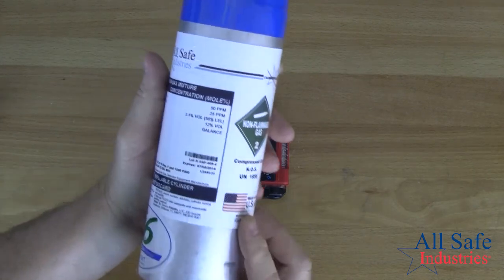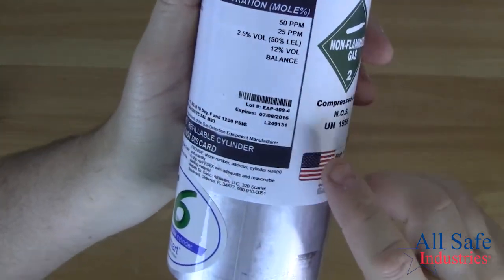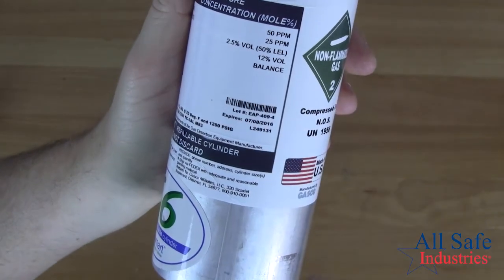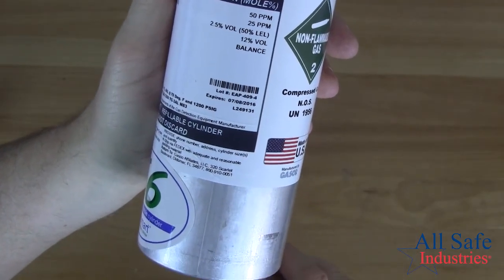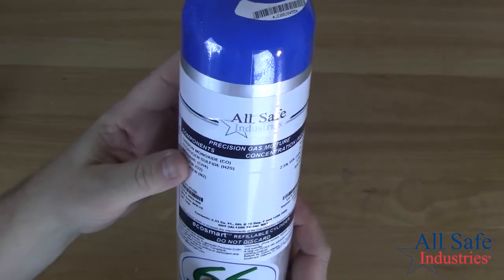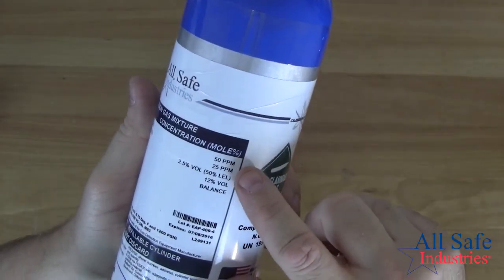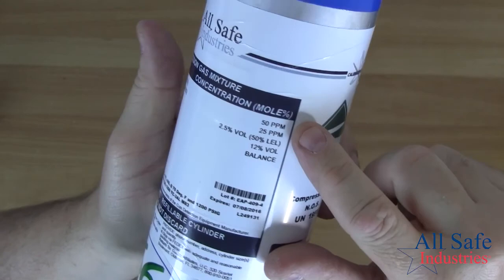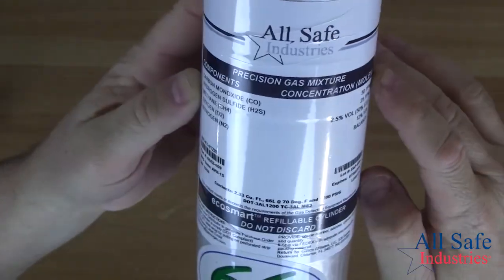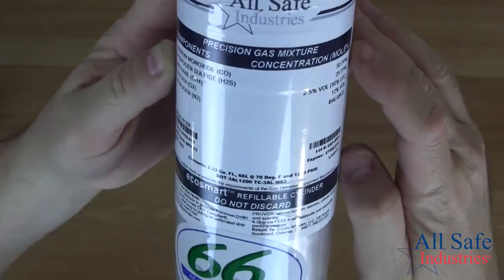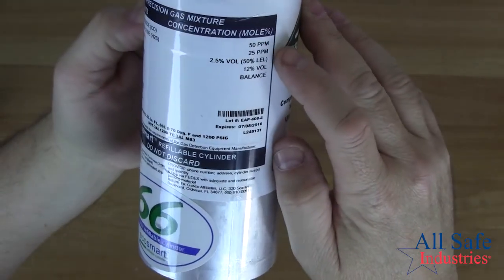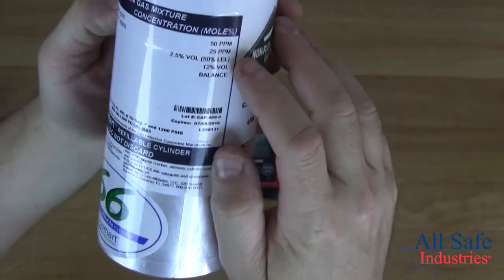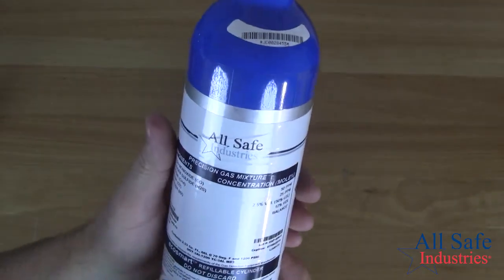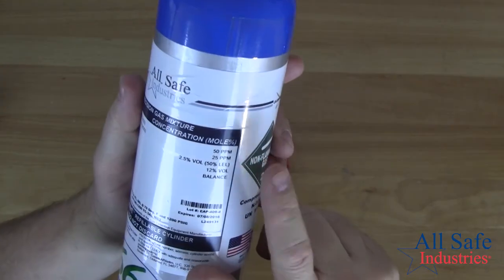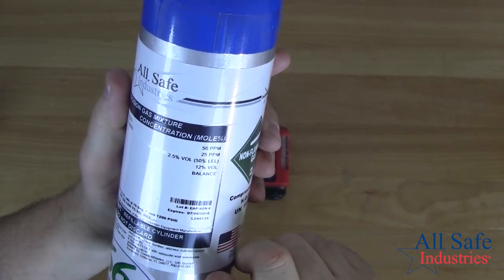And remember, like we mentioned earlier, you're going to want to check the expiration date on that cylinder and make sure you've got good calibration gas. You don't want to calibrate your meters on expired cal gas. So make sure your cylinder is good to go, and make sure you're using the right concentrations. This is what the factory recommends: 50 parts per million CO, 25 parts per million hydrogen sulfide, 50% LEL methane, and 12% oxygen with a balance of nitrogen. So we're using the factory recommended calibration gas. Even though it says All Safe Industries, it is the right gas according to the factory, RKI.